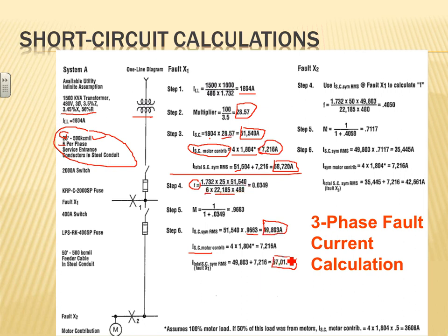It's cumbersome, but it's really nice for us as engineers to go through it just to verify, because we don't see the math behind all the SKM. You hit comprehensive calculation and it gives you all the calculation, so you don't have to worry about this one. Then you go to X2 here. So this is calculation at 2 points. Here I have a 400 amp. I moved another one set of 500 kcm, and I need to add its contribution. So here's a 500, multiplied by 1 because there's only one set. It knocks it down again after you add the contribution of the motor. Look at that, we knock it down to 42.